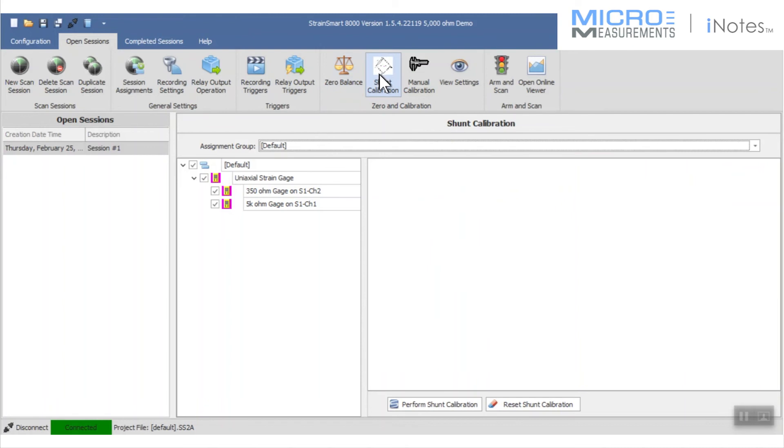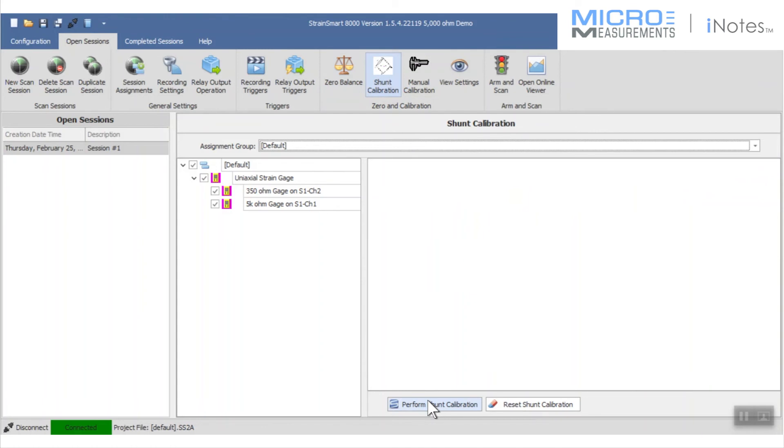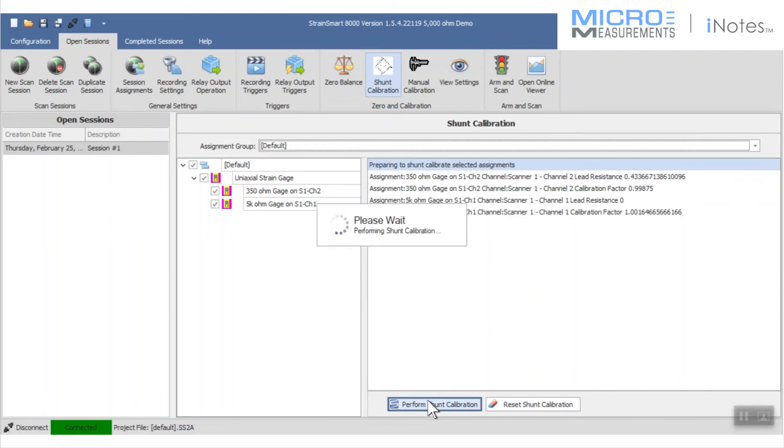Then I'm going to ask it to perform a shunt calibration. The shunt calibration, if you're not familiar with it, is paralleling in a very precise known resistance that creates a very precise known strain level. As I did in the previous screen, I told it what to expect. If it makes the measurement and finds something dramatically different, it's going to report that back to me.